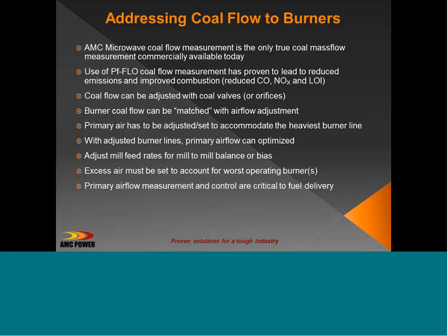The other thing that we find is that the primary air, even though we can measure it very accurately using airflow equipment like ours, how much primary air you need really can't be determined until you look at the fuel particles as they move to the burner. So we're going to go through some of this. Most of this presentation is going to go into data where we have used the equipment.